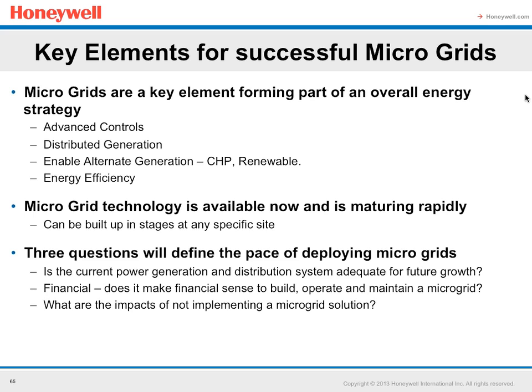Distributed generation allows you to bring generators on one side of the campus online through the microgrid control system and actually power buildings elsewhere if more power is needed than that generator uses locally. You're allowed to mix and match, whether it's CHP, a turbine, or a diesel. Even your PV can stay online during a power outage once you're separated from the grid, and the microgrid controls will manage that power as well.